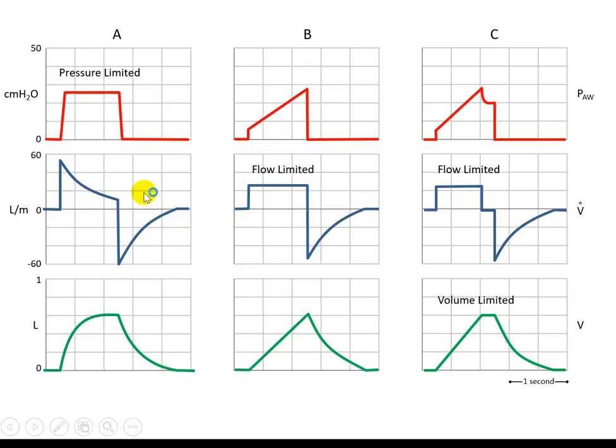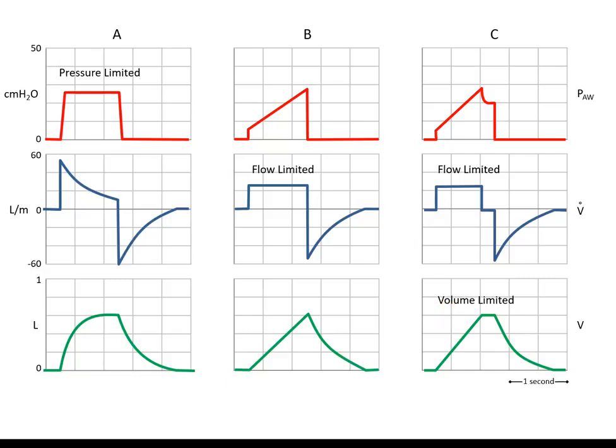After the breath is initiated, there could be another variable called the limit variable. That limit variable could be a limitation on the pressure — the pressure goes up to a certain level and is maintained, such as in pressure support. It could also be flow limited, where the flow goes up to a certain value and does not go above it. Or it could be volume limited, where the volume reaches a certain value and does not increase above that value.